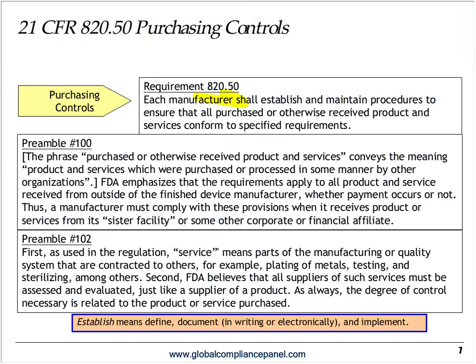So preamble paragraph number 100, and there's hundreds of sections in the preamble as it went through all of the regulations, says that products or services which are purchased or processed in some manner by another organization. So what this means is that this is anything that comes from outside the device manufacturer, and it's got nothing to do with payment. One of the things that often happens is people ask the question, well, if I get something from inside another division of my company and no payment occurs, I don't actually write a check, does it fall under purchasing? And the answer from FDA is yes.